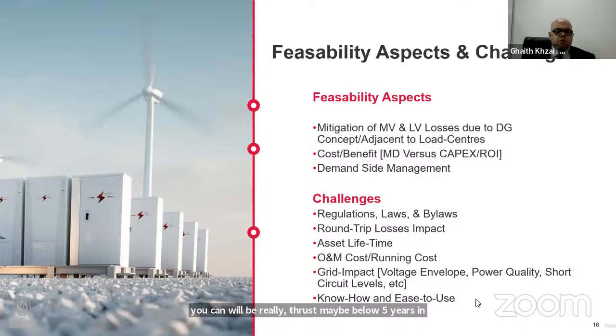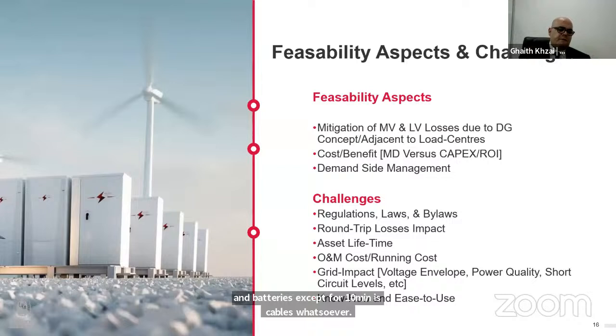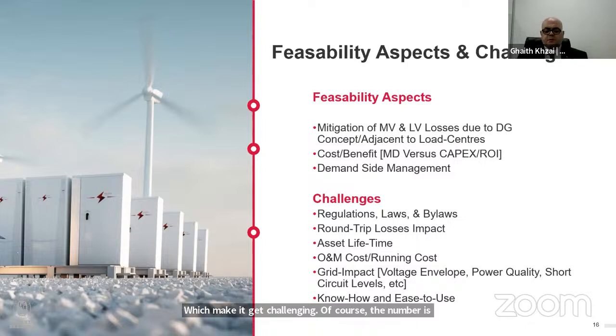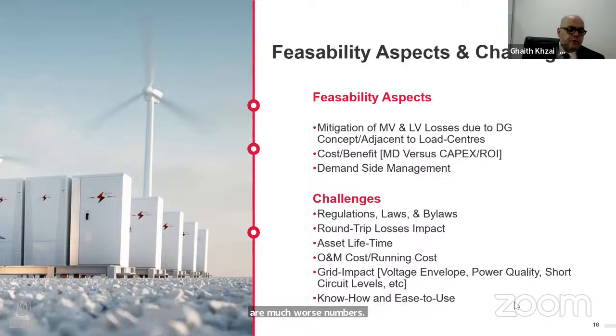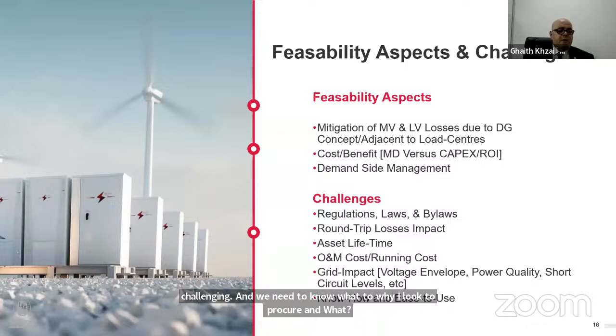From the challenges point of view, when it comes to BESS on the distribution grid, the majority of countries in the world still do not have mature and sufficient regulations, laws, and bylaws. Also, there are round trip losses, which are the losses to charge the battery and then discharge it again, passing through a transformer, the batteries themselves, internal losses, cables, whatever. They have reached in many cases more than 14 or 16%, which makes it challenging. Of course, the number is only indicative. There are much better numbers and much worse numbers for those losses. From the asset lifetime point of view, it is really challenging, and we need to know what to buy, what to procure, and what quality checks by OEMs are needed to secure a longer battery energy storage system lifetime.